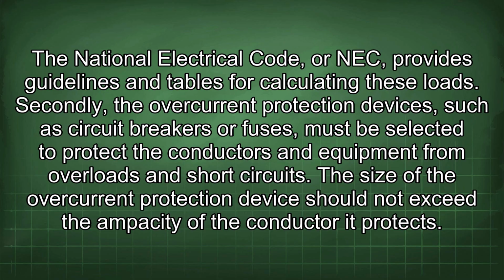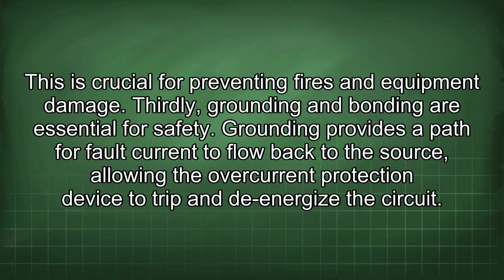Secondly, the overcurrent protection devices, such as circuit breakers or fuses, must be selected to protect the conductors and equipment from overloads and short circuits. The size of the overcurrent protection device should not exceed the ampacity of the conductor it protects. This is crucial for preventing fires and equipment damage.